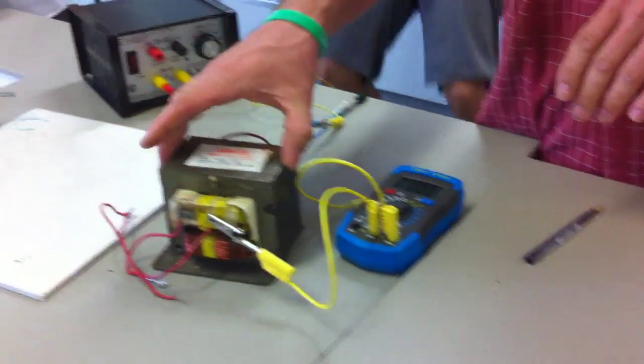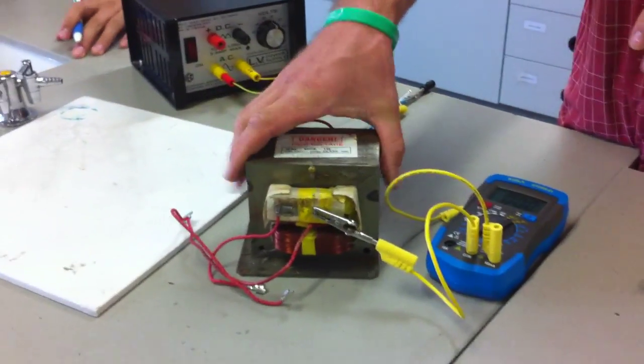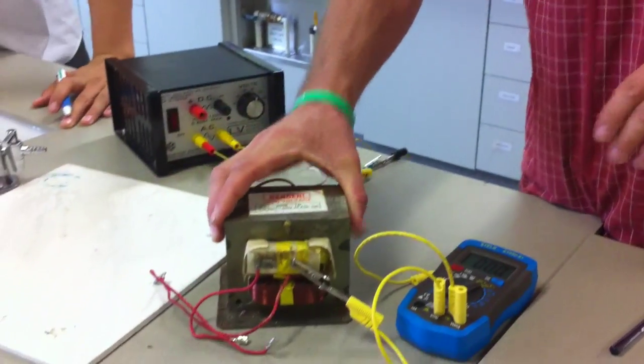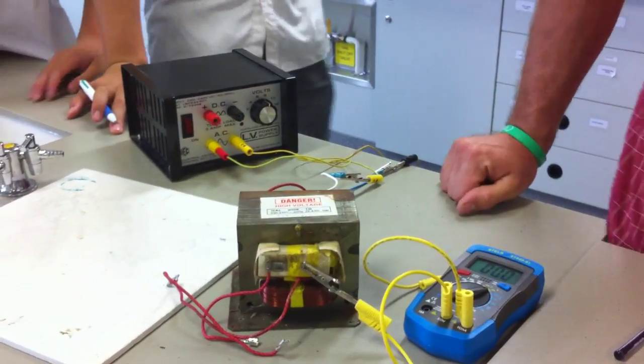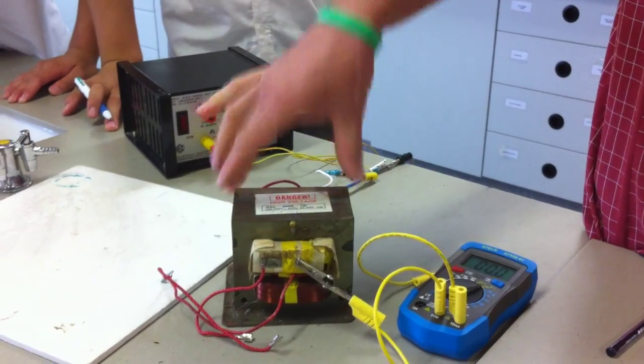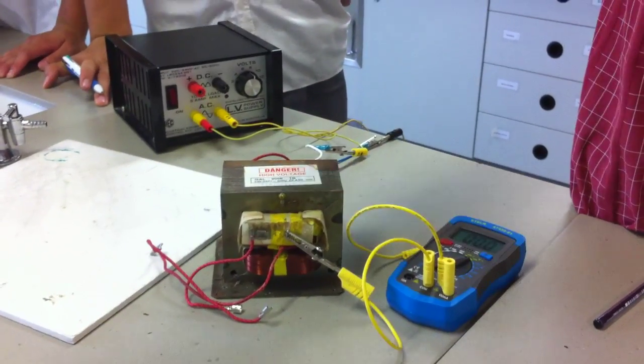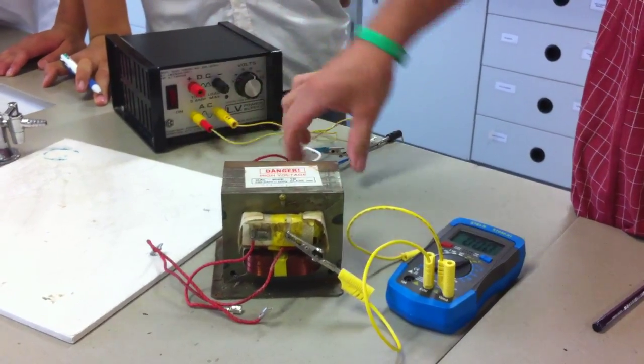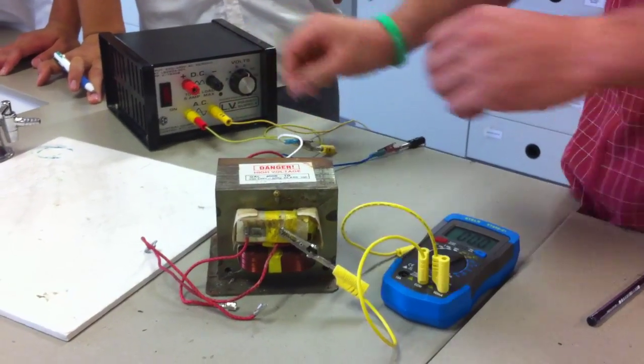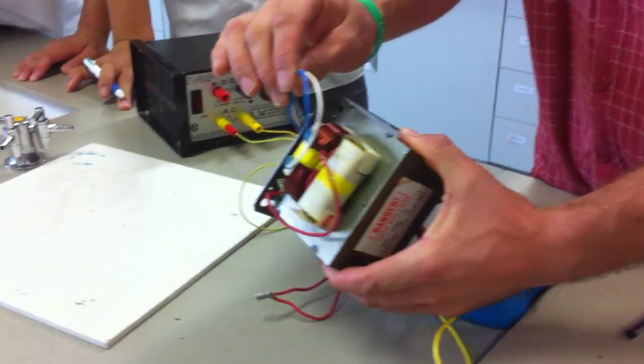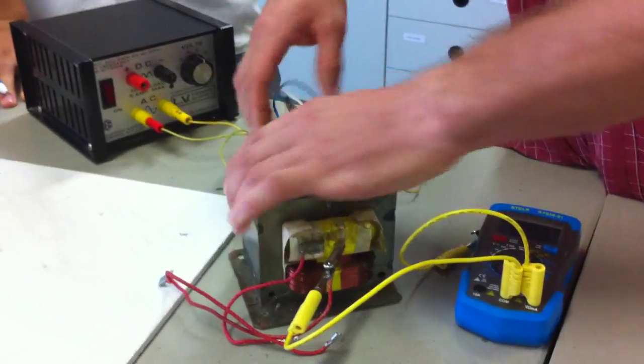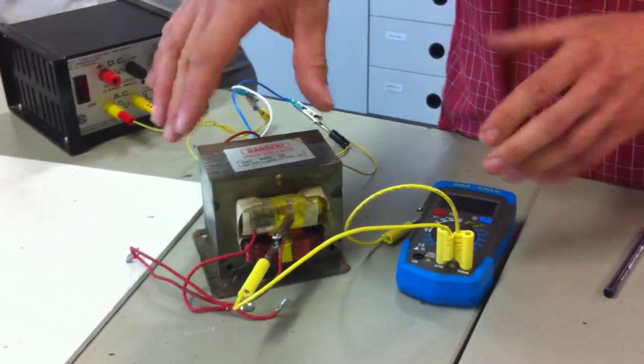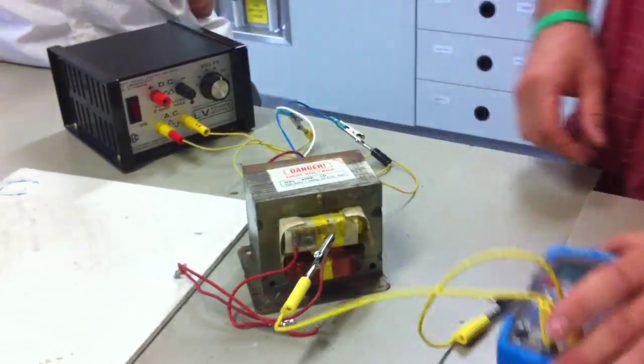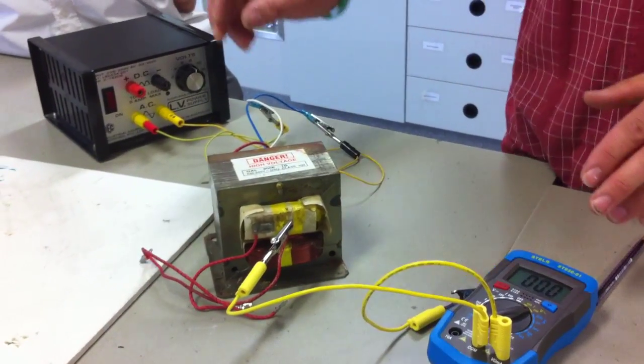Okay, this is an AC transformer. It's been removed from a microwave oven. This transformer generates high voltage in the oven, taking 240 volts normal input on this side up to about 2,400 volts on the output side, which is used for generating the microwaves in the oven.